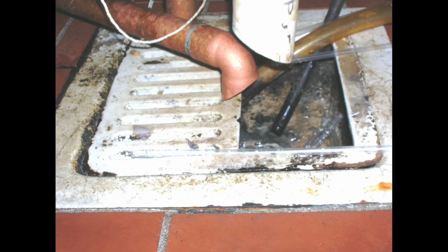Where are the drain locations, and how are the cleanouts set up for the bar? Can the plumber get to them, clean them out? Because you know you're going to get straws, fruit, and all kinds of stuff down those drains. And those drains are a great harborage for fruit fly generation and have to be cleaned. And the best way to get some of those drains cleaned is also a wet vac, but not when you're open, because the odor you're going to send through the restaurant is terrible.